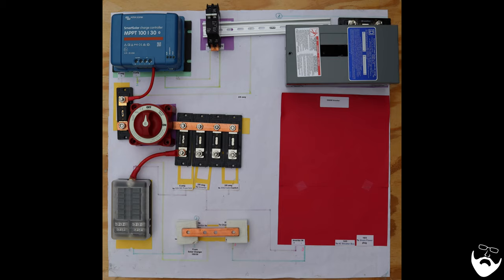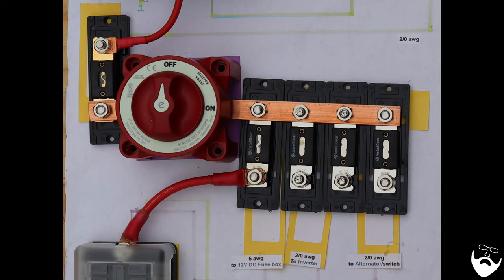After the disconnect there is a bus bar with room for four fuses. Three of them are needed, one is there for a future use just in case I need to protect a circuit with a different fuse rating. Remember, always design with options so you have the flexibility to make changes in the future without having to rebuild the entire system.